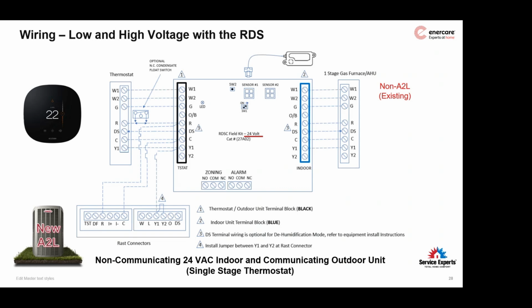The boards look very similar. Just the wiring is a little more inclusive, right? We have our standard signals that we would normally have. So as you can see, this is wired as an air conditioner. And in order to get full variable capacity out of this variable unit, Y1 and Y2 outside need to be jumpered. Not much of an ask, pretty simple stuff. Make sure Y1 and Y2 are jumpered outside. And then the control board outside in this communicating piece of equipment will monitor suction pressure to make sure that it maintains a very specific suction pressure, or back pressure, so that it'll move through its variability based on the pressure transducer that's in the unit.